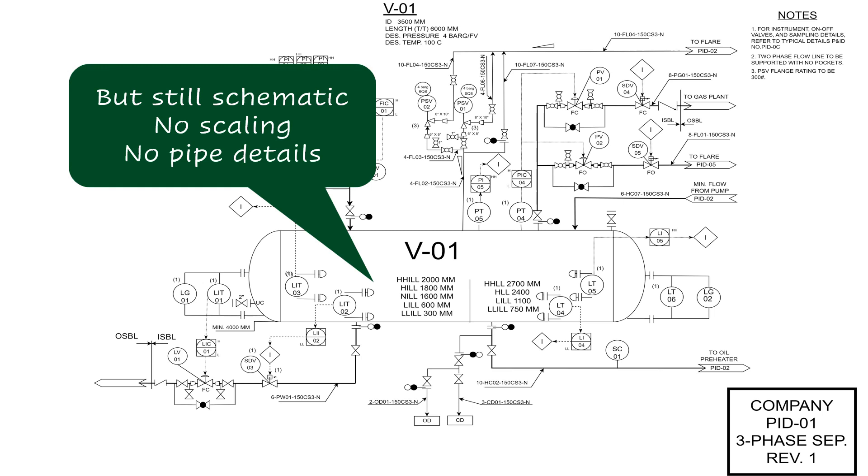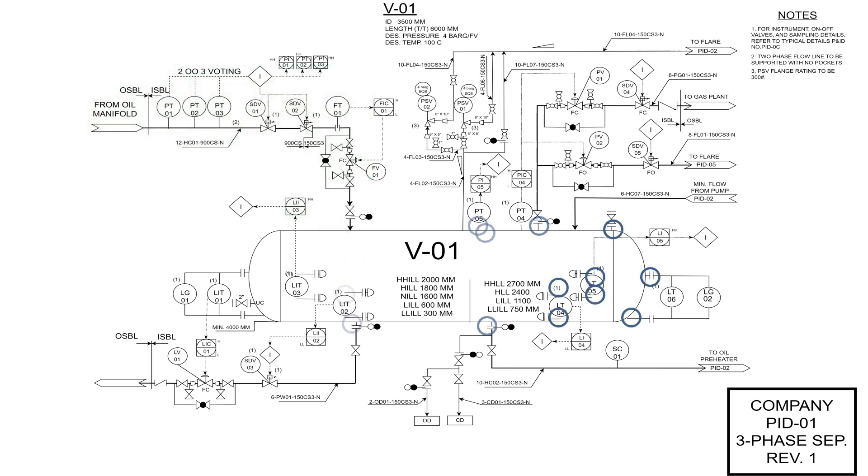For example, the P&ID is expected to show all the nozzles in any piece of equipment, and what these nozzles are connected to. Shall they be connected to process lines, or to utility lines, or to instruments, or to pressure safety valves, shall they be just blinded? All this should be reflected on the P&IDs.